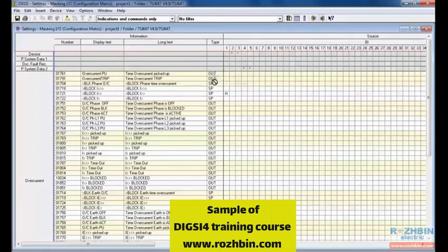If the type of signal in this section is specified as SP or single point indication, it means that this signal can be used for binary input. But if it is specified as out type, this signal can be used for binary output or LED. The next column is for source, which itself has three columns. The first is binary input, the second is function key, and the third is CFC.